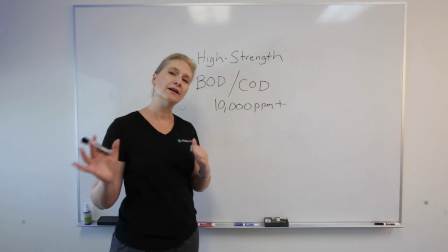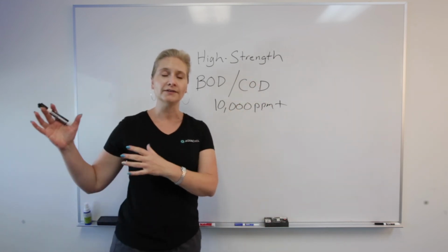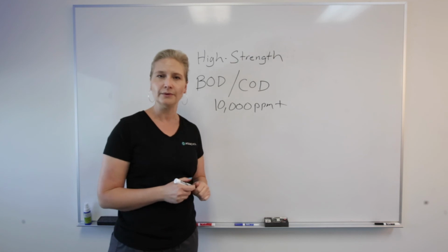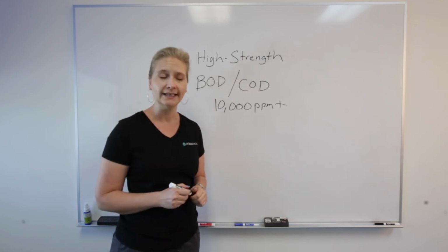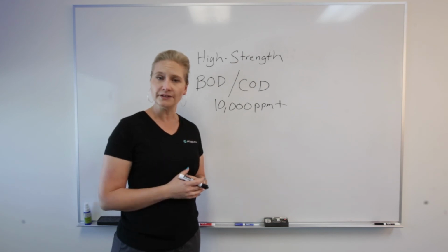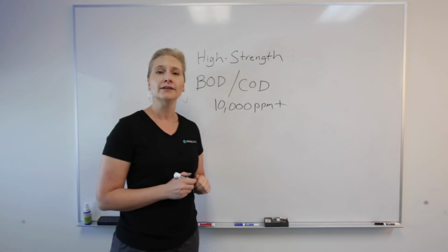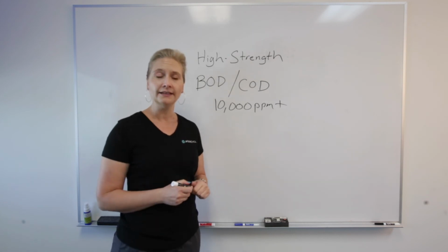The other way is to concentrate. So everything goes to your floor drain, to your sump. You run it through a concentration process, which is typically going to be a membrane filtration process. And then the clean water can be brought back in for reuse, potentially after some disinfection, or sent to sewer at very low cost. And then the brine can go to an alternative treatment strategy like AquaCycle.